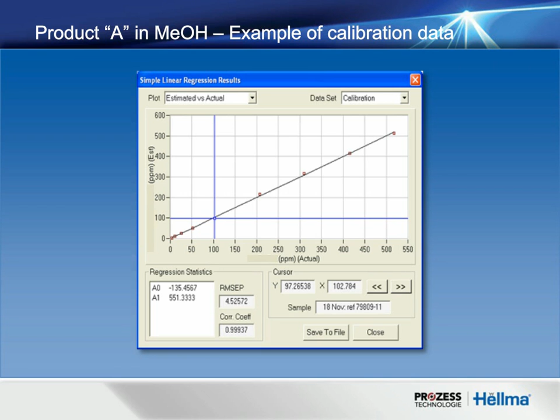And then applying this model. Now on the left, when we're just looking at the measured absorbance we're just looking at the broad band of, in this particular case, there was a 275 nanometer absorption band that we can then correlate so that we can predict concentration. And in this case, there would be two uses: there's the cleaning validation, which is measuring the elimination of product, but it's also a real-time cleaning monitor or cleaning status indicator.